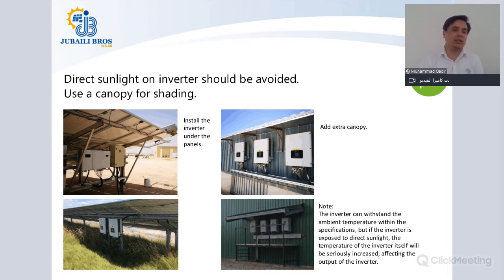If you're installing on a wall which is facing the sunlight, then you must make an extra canopy on top of the solar panels and solar inverters, and you also have to consider the spacing mentioned in the Huawei user manual on top of the solar inverters. For example, the 60 kTL Huawei inverter tells you that you must keep a spacing of around 500 mm for the proper cooling of the inverter. That is a must.